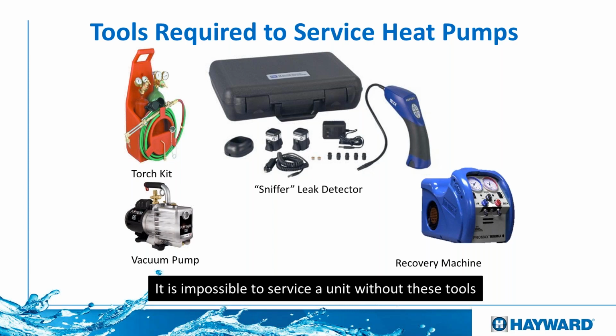And then we're also going to need a recovery machine and a vacuum pump. A recovery machine is used, before we open a refrigeration system, to take out any refrigerant that we still have, because that refrigerant can be reused to charge the heat pump once again. And then with the vacuum, we draw a vacuum on all of our refrigeration lines to make sure we take out all of the moisture before we recharge the unit. So again, remember, it is impossible to do service without all of these tools once you get into the refrigeration lines.